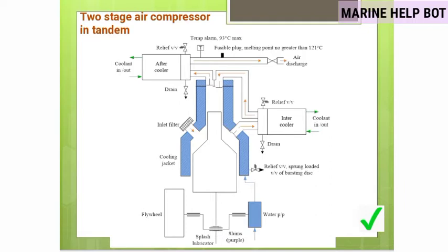The tandem type air compressor uses a double-acting piston where one side acts as the first stage and the other as the second stage. Every cycle involves suction and discharge. Air enters from the inlet filter, is compressed and passed through the intercooler where temperature is lowered, then passes to the second stage, is compressed again, passed through the aftercooler, and received in the receiver.